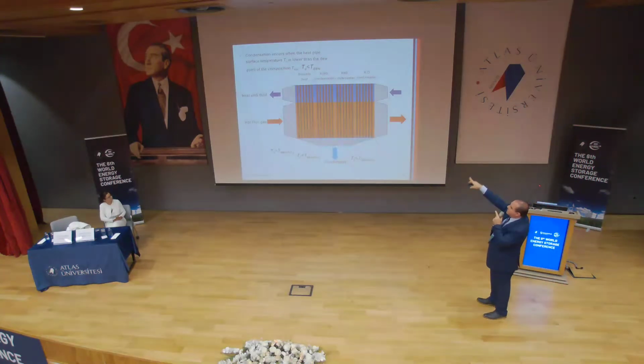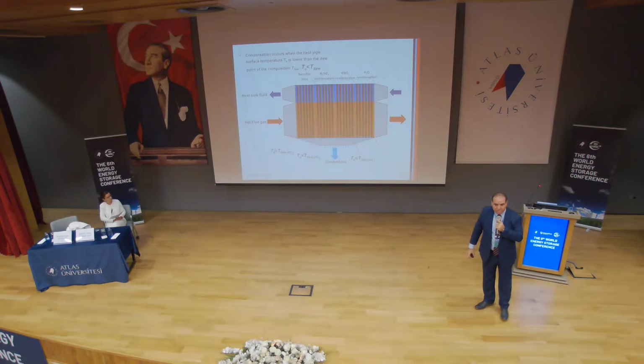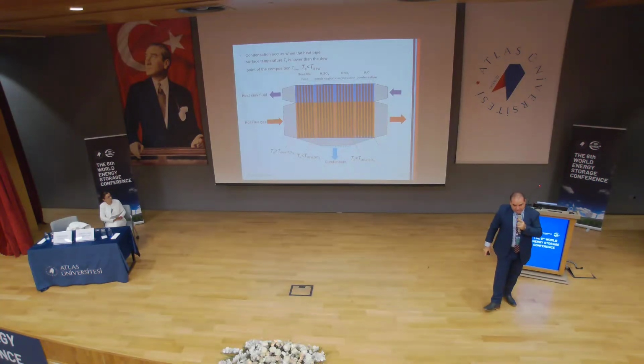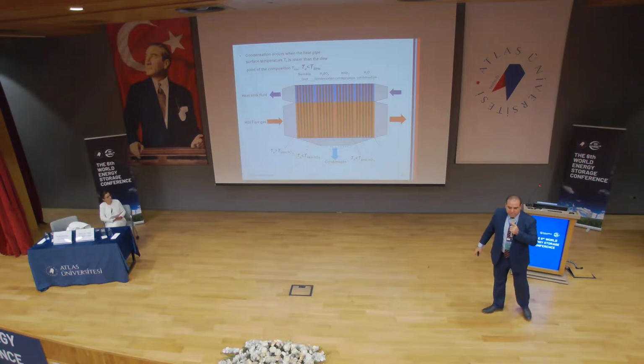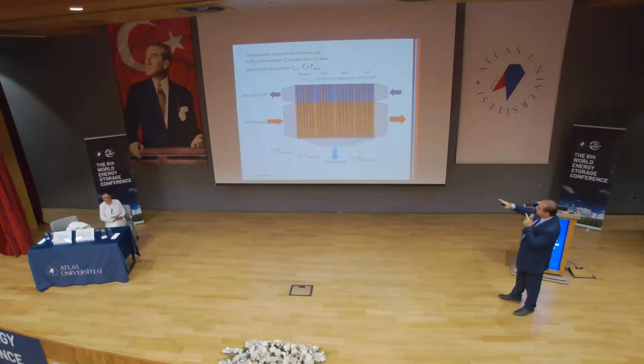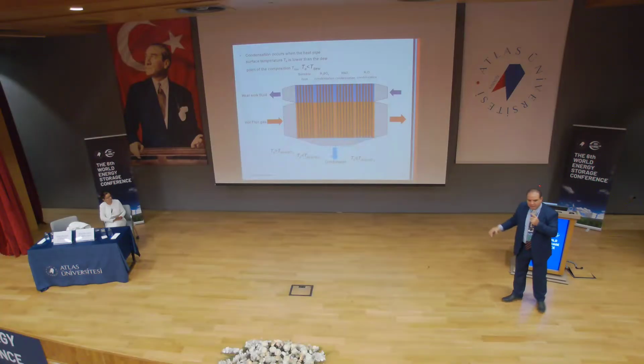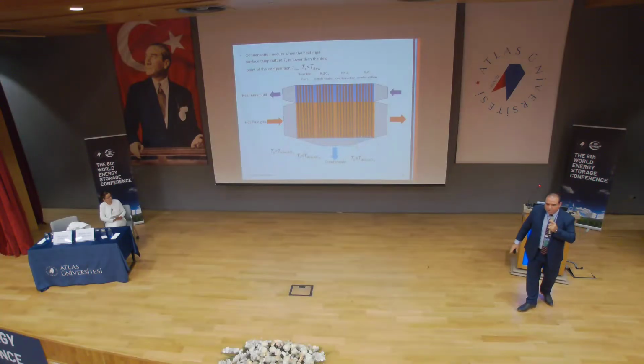So stage one of the heat exchanger, I'm just cooling without any condensation, so I don't need premium metals. Stage two, I condense the first acid, which is usually sulfuric acid, H2SO4, so for that I use metals that can withstand the corrosion. Stage three is where nitric acid more commonly condenses, which has a lower dew point.